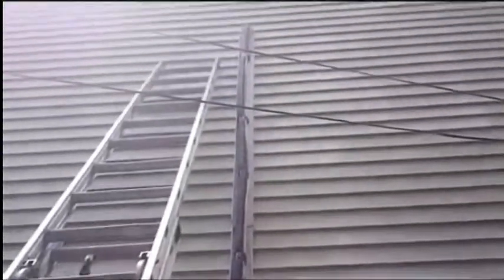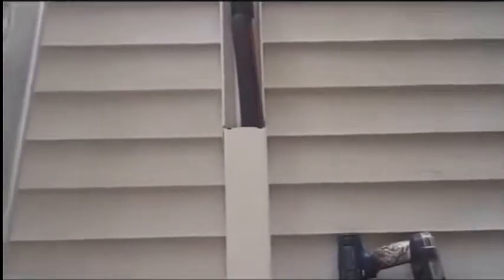Alright, I got my speedy channel up there. That's the first piece I snapped on. You see the line set and everything else is in there now, so I just got to cover it up. Put a couple hanger straps midway up there just to kind of take some of the tension off of it. And had to cut the speedy channel off so it'd be about 18 inches above the ground there. You don't want to get it too close to the ground. Just paying attention that I'd cut off the end that's going to be going into a coupling so you don't have any rough edges sticking out.